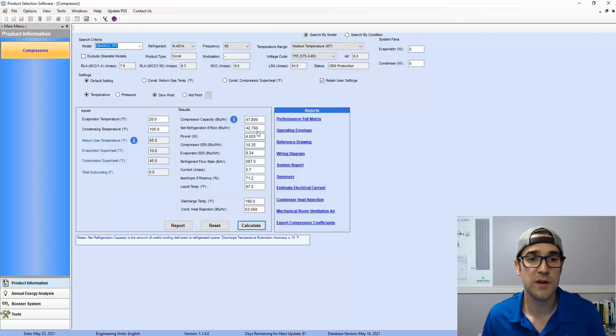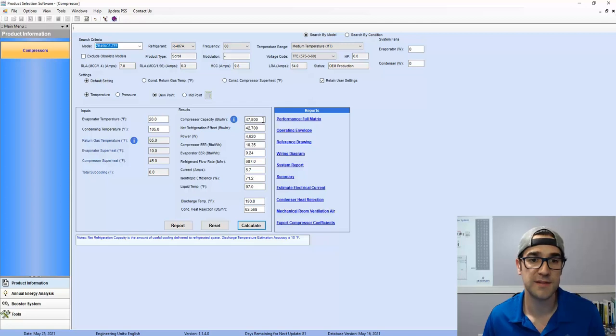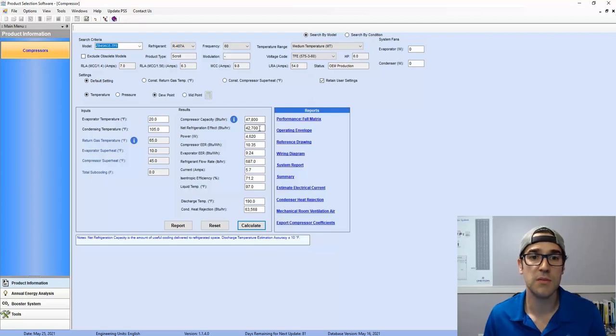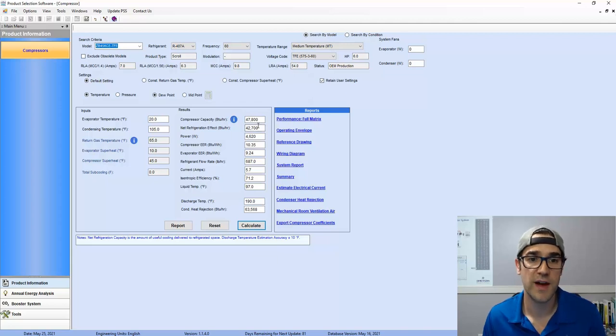Well, we're looking at 47,000. So we're almost 20% higher than our compressor capacity. And right here, we're probably 5, 7% higher here in our evaporator.